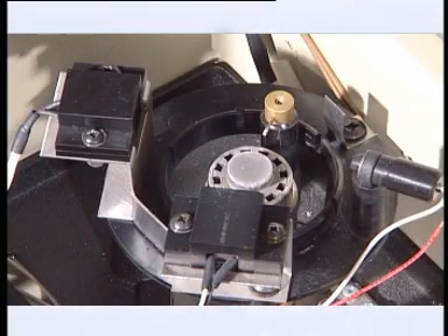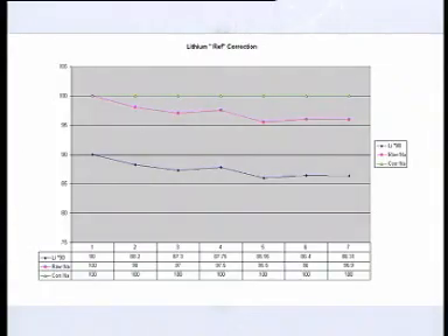The lithium detector is permanently monitoring the flame alongside the sodium and potassium detectors. As the flame and instrument changes temperature, the emission of all 3 elements will change. If we multiply the sodium and potassium result by the deviation from 1.000 of the lithium channel, we can eliminate the drift component of those emissions.